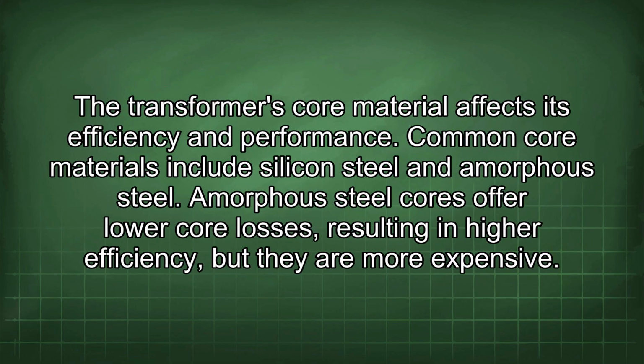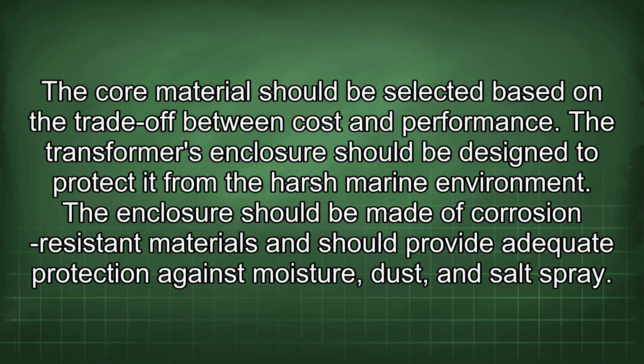The transformer's core material affects its efficiency and performance. Common core materials include silicon steel and amorphous steel. Amorphous steel cores offer lower core losses, resulting in higher efficiency, but they are more expensive. The core material should be selected based on the trade-off between cost and performance.